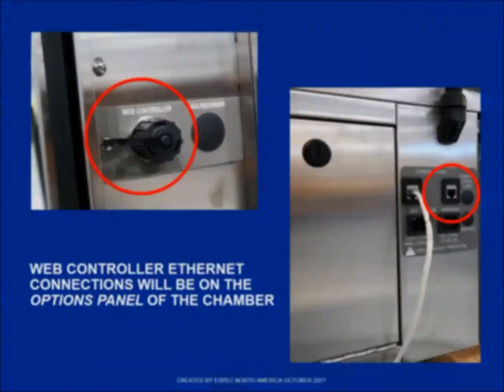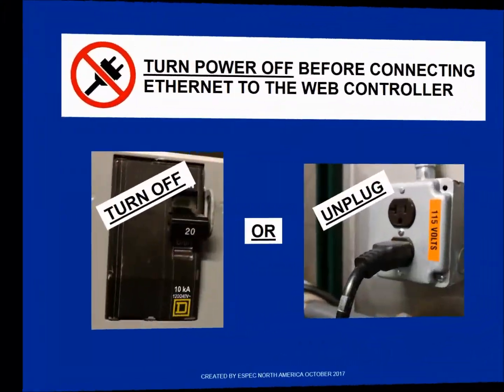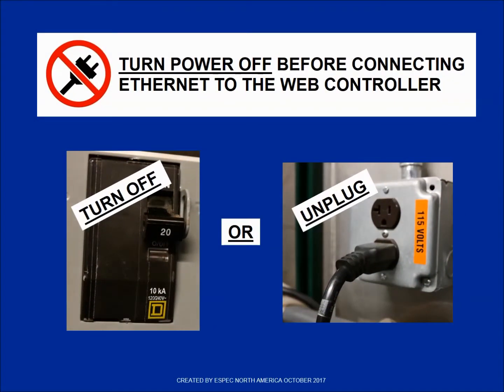To assure the web controller is detected and the web controller location can be found, turn off all the power to the chamber before plugging in the controller Ethernet cord.